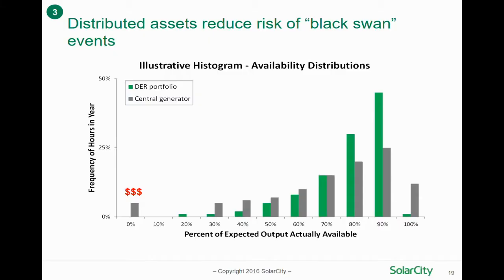Reliability and resiliency planners in the grid today talk about contingency planning, where they plan for N-1, N-2, or N-1-1. That means if you have a system you're trying to manage, you plan for the worst case scenario when your biggest asset fails, and you need to make sure the grid still works. In PG&E territory, they have plans for when Diablo Canyon goes out - can the rest of the system manage all that load pouring onto it? That's one of their N-1s.